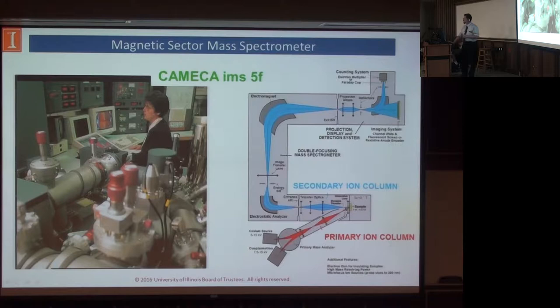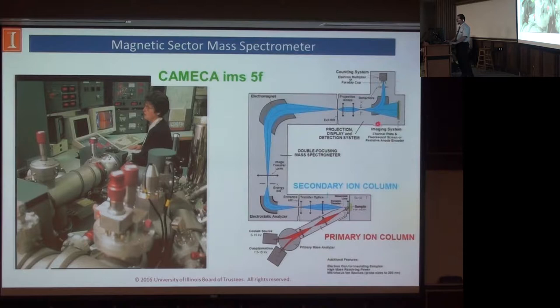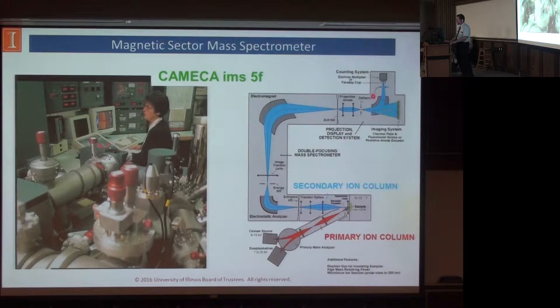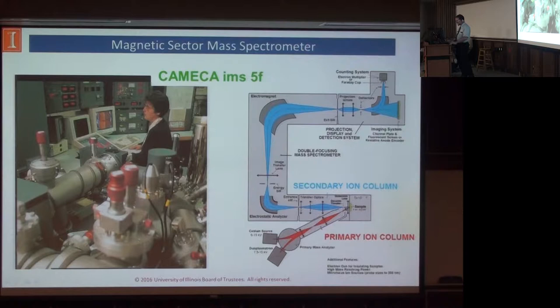The Cameca IMS-5F that we have is very good for doing dynamic SIMS. We send a continuous beam in — either cesium or oxygen — to hit the sample surface. Then we pull out the secondary ions and bend them through an electrostatic analyzer, an electromagnetic analyzer, and through a final slit before they hit one of our detectors. You're only measuring one mass at a time, though you can quickly switch between them, so it's very useful to know what you want to look for before you put your sample in. For detectors, we use an electron multiplier for 0 to 10^5 counts per second, or the Faraday cup for 10^6 or better.